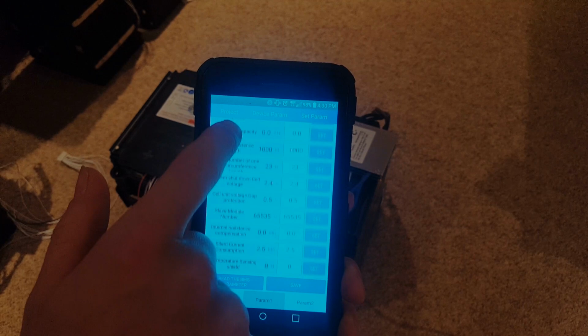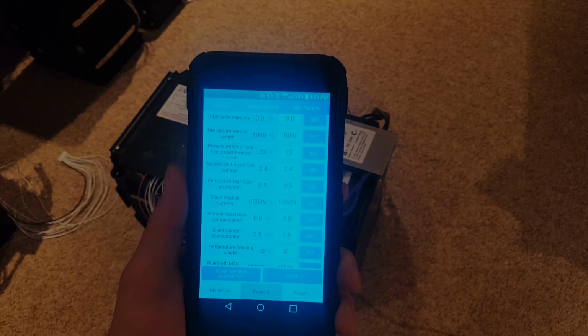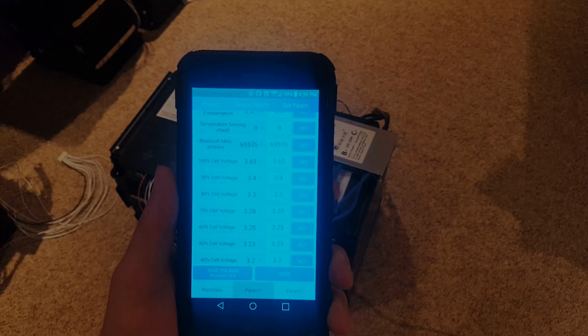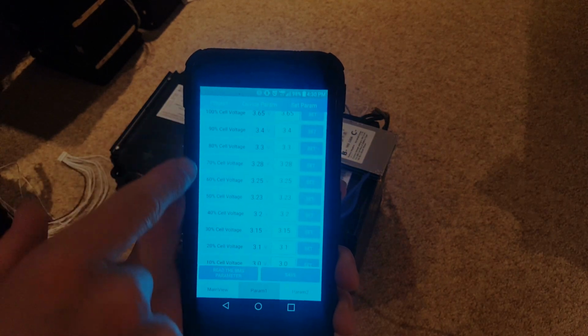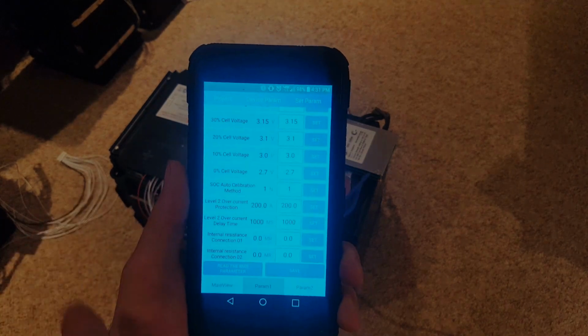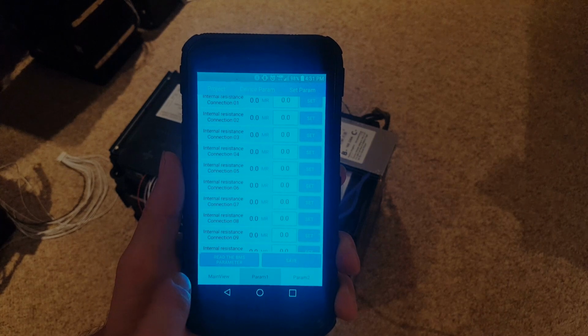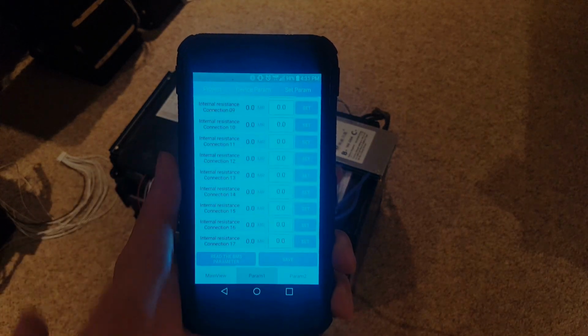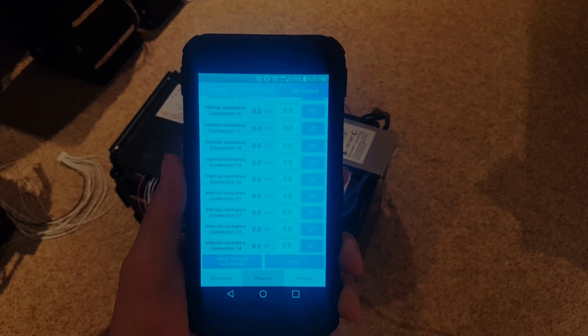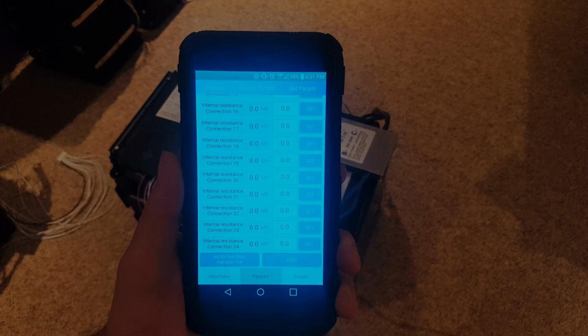It kicks the balancing in, and I think as we cycle these I'll get a better feel for the way this BMS works. It gives you percentages based on cell voltage, and it actually has a coulomb meter that measures the amperage coming out and going back in, giving a more accurate capacity reading rather than just using voltage, which is especially useful for these because they have an extremely flat discharge curve.